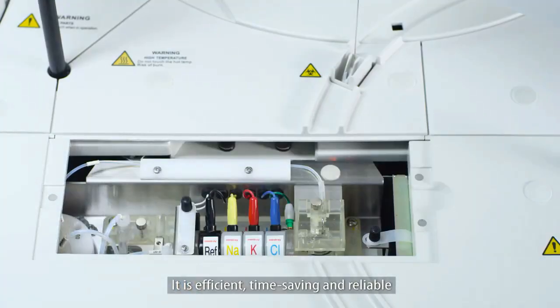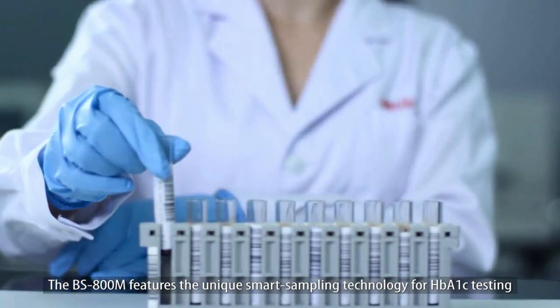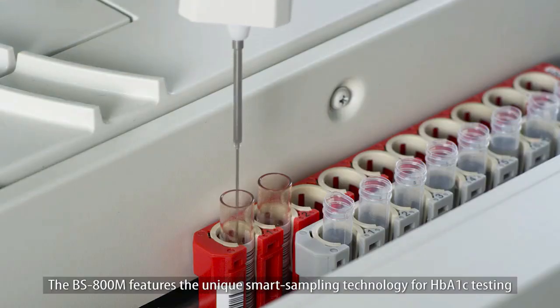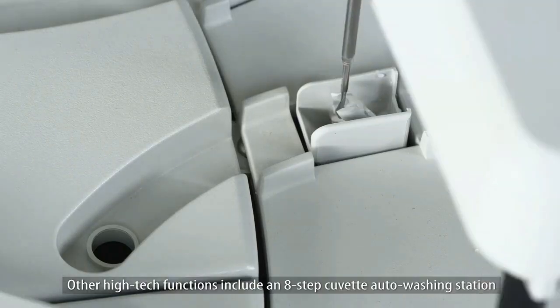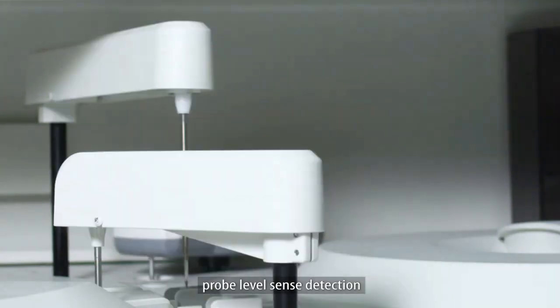The indirect ISE module only requires 22 microliters of sample — it is efficient, time-saving, and reliable. The BS-800M features the unique smart sampling technology for HbA1c testing, which allows automatic preparation of hemolysate on board.